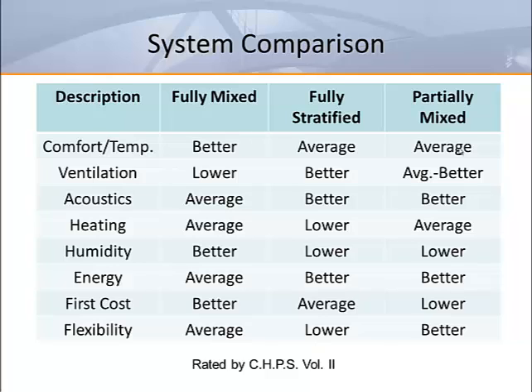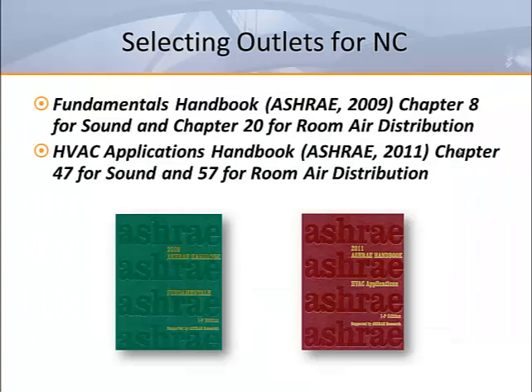Displacement ventilation and underfloor air distribution have lower operating pressure and may be lower in energy cost. Fully mixed systems generally have a lower first cost. Underfloor offers the greatest flexibility when churn is required, such as in a computer lab. Additional information can be located in the ASHRAE Fundamentals Handbook 2009, Chapter 8 for sound and Chapter 20 for air distribution, and the ASHRAE Applications Handbook 2011, Chapter 47 for sound and Chapter 57 for room air distribution.